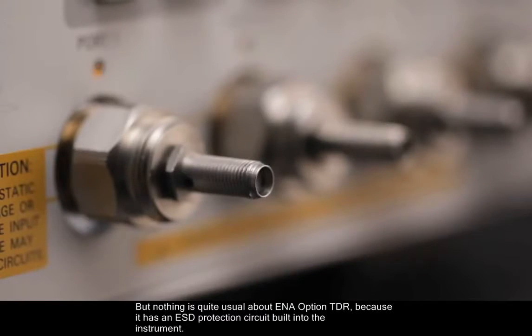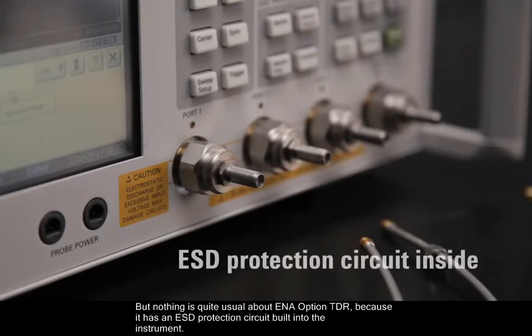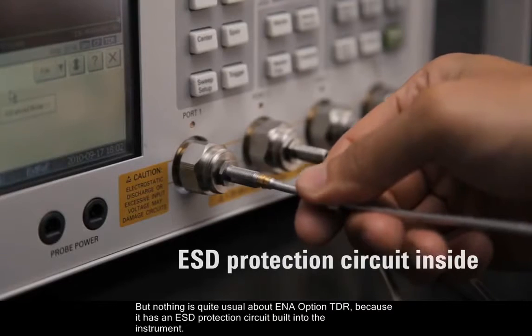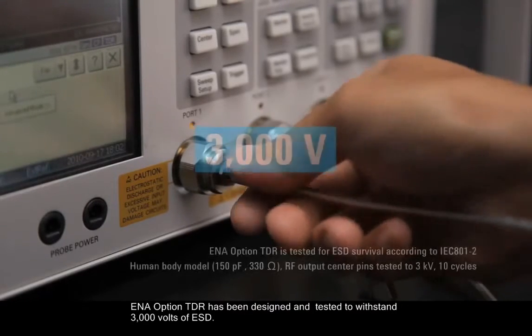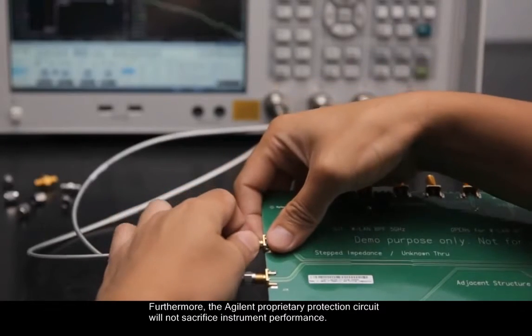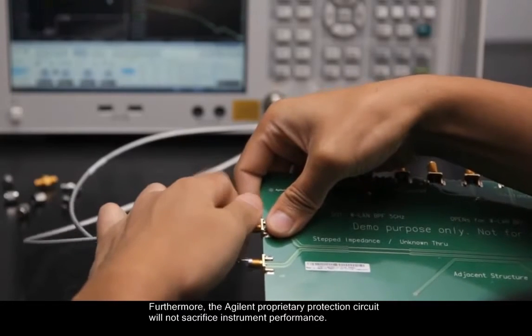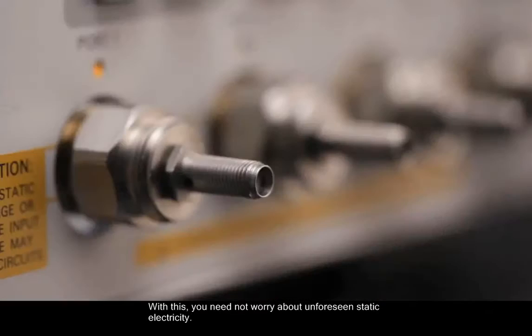But nothing is quite usual about ENA Option TDR because it has an ESD protection circuit built into the instrument. ENA Option TDR has been designed and tested to withstand 3000 volts of ESD. Furthermore, the Agilent proprietary protection circuit will not sacrifice instrument performance. With this, you need not worry about unforeseen static electricity.